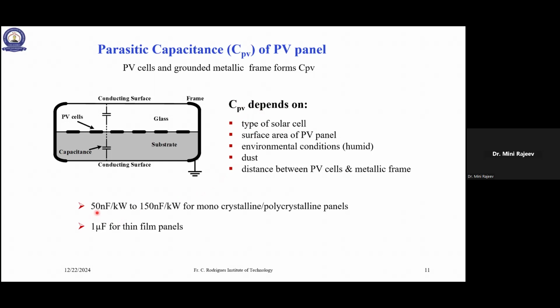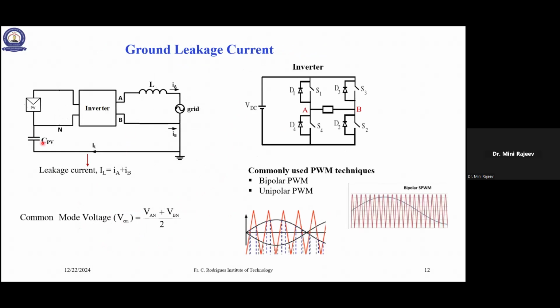And these values are 50 nanofarad per kW to 150 nanofarad per kW for monocrystalline or polycrystalline panels. And since the thin film area is lesser, it is higher. It is around 1 microfarad for thin film panels. So now we know what this parasitic capacitance is, and that it exists when you have a PV grid system.